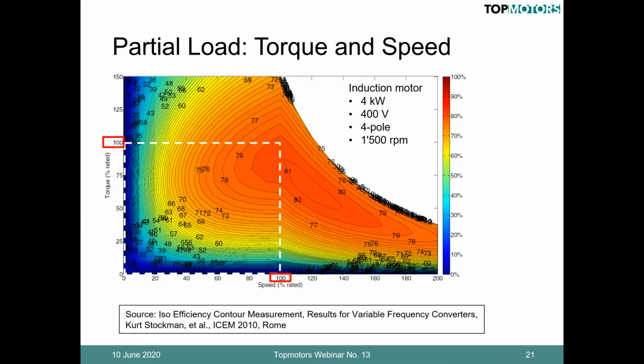Now, normally all business with motors and converters and their respective driven systems deal with that square. And we have taught people for a long time you shouldn't oversize your machine, because in this upper third of the white square, you have a relatively good system efficiency. System efficiency is the combined efficiency of the converter and the motor. In this case of a 4 kilowatt motor, you are certainly above 75% and you reach about 80% at the top.